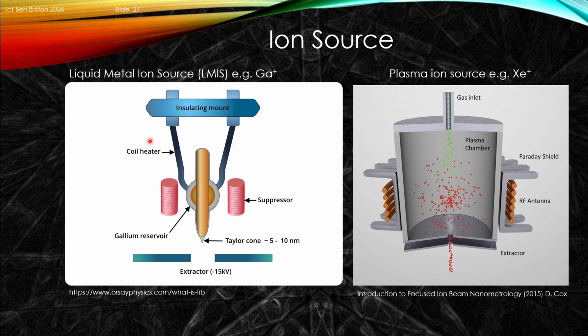Now, if we look at our sources, this is where there's just the subtlety of the two different source types. Let's focus on the left hand. This is the liquid metal ion source. Basically, we have a tungsten hairpin coil, and we have a gallium reservoir, and that gallium reservoir enables us to effectively wet the end of our tungsten hairpin. So we can basically have this wet. It forms a small, very sharp so-called Taylor cone, and as the ions are extracted by applying a high voltage through the extractor voltage here, they are pulled off the surface of the Taylor cone.